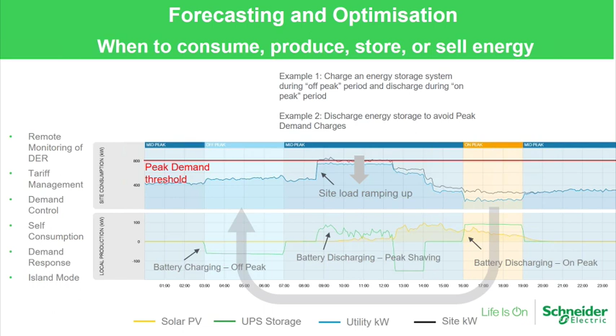That's being met by the battery discharge and also some of the PV as well. The time in the middle of the day where the battery is discharging, from 9 till 12, that's helping to offset and drive down the peak demand from the grid, peak shaving. If you look at the red line, you've got peak demand between 9 and 9:30. You can see the site demand is actually higher, but the grid import is lower because you're discharging the battery, so you're not exposed to the high charges you would have without that battery there.